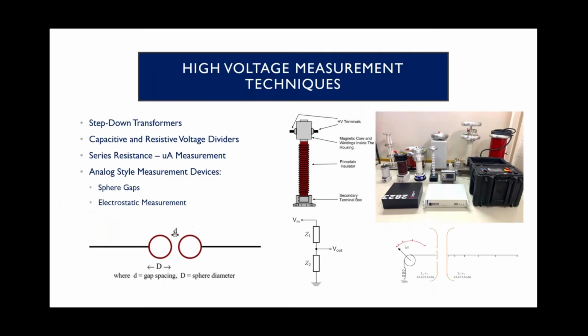More standard voltmeter, so down to a more reasonable level that there are a lot more devices capable of measuring that. And then they ratio it up mathematically based on how that transformer winds it down. Similar concept with capacitive and resistive voltage dividers. Essentially, you're going to divide the voltage down through a specific resistance and or a capacitance. Once again, to a level that can be measured with a separate, more standard voltmeter.